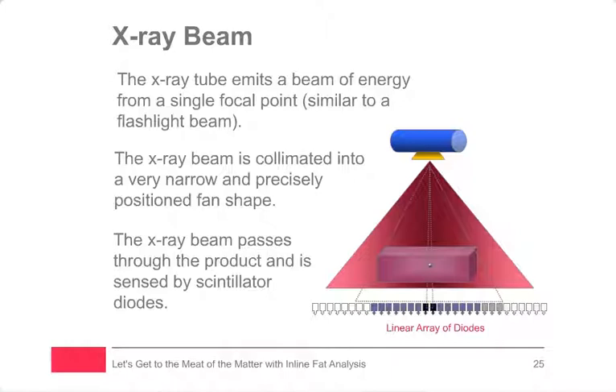If we think a little bit about how the actual contaminants are identified in the actual product, we can see, again, an X-ray tube at the top, and a linear array of diodes at the bottom, our detector array. On the left and the right-hand side of the actual fan beam, we can see that none of the X-ray energy generated by the tube is absorbed by any product. This leads to an output from the individual diodes being very low. This is represented graphically in white. As we move into the center of the triangle below the tube, we can see that some of the actual X-ray energy will be absorbed by the actual product itself. As a consequence, the amount of X-ray energy that arrives at the diode is slightly less than at the outside. Therefore, the output from the individual diode arrays is slightly different, and it's represented in grey.